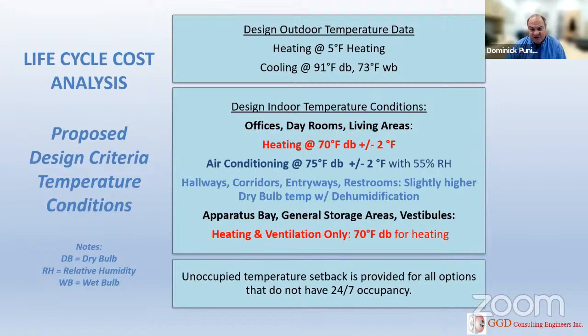Hallways, corridors, entryways, restrooms, they'd be slightly higher. We're not typically providing the same level of air conditioning. Sometimes those are passively conditioned, but all that air is still dehumidified. And then the apparatus bay, general storage areas, vestibules, those are typically just heated and ventilated and made to 70 degrees dry bulb. So again, this is what all options would be studied under, and it's really driven by the energy code. Also in the energy code, unoccupied temperature setback has to be provided for all options and all areas that don't have that 24/7 occupancy. So certainly if an area is fully occupied, it's going to be maintained at the occupied temperatures. Next slide.